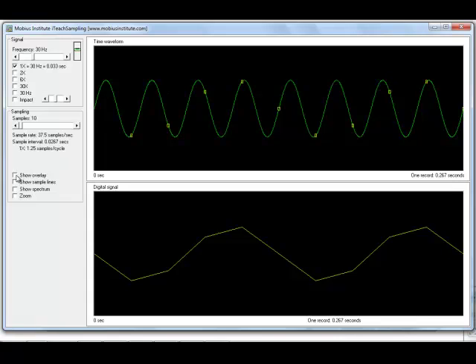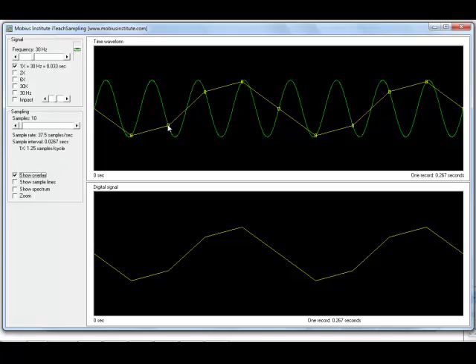If we were to reconstruct the waveform from these yellow points, this is what we end up with. If I draw straight lines between each of these points — which is all the software is doing inside either the analyzer or the vibration analysis software to create that time waveform — it's just joining the dots. But is that signal equal to the green signal? No. If I did an FFT of that, it'll tell me that I've got a frequency which does not exist. And this is the problem with aliasing — we are seeing one thing that does not actually represent the data.